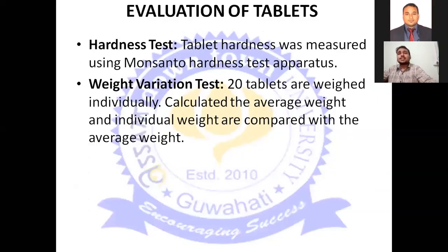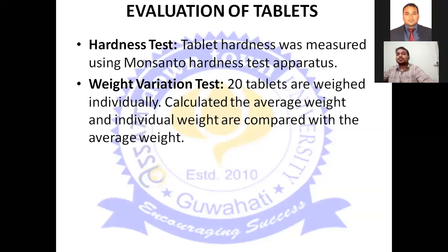After preparation of the tablet, we are going for the evaluation of tablets. The first evaluation is hardness — the hardness of the tablet is characterized by the Monsanto hardness tester. I have shown in the video how we can calculate the hardness through the Monsanto hardness tester.